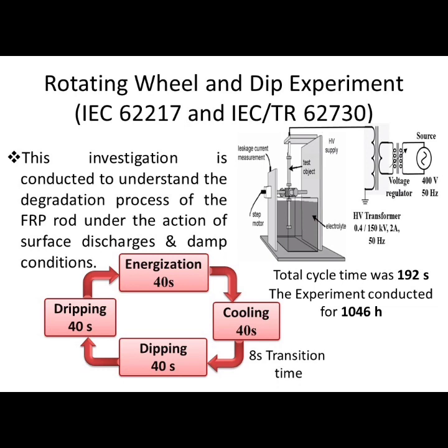Then the dripping stage for 40 seconds. Then the high voltage energization, where the high voltage will be applied on the sample for 40 seconds. And at the end, we have a cooling stage for 40 seconds. The period of each stage is 40 seconds with 8 seconds transition time, so the total cycle time will be 192 seconds. This experiment is conducted on the bare FRP rod samples for 1046 hours to evaluate their performance under the worst case scenario, where the FRP rod will be exposed to a conducting water film and electrical discharges.